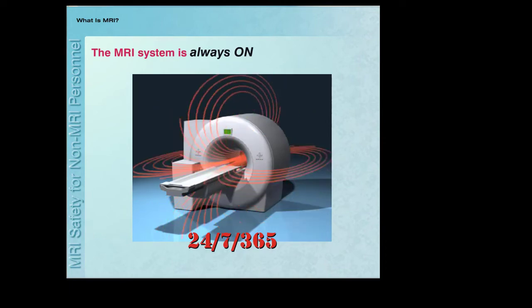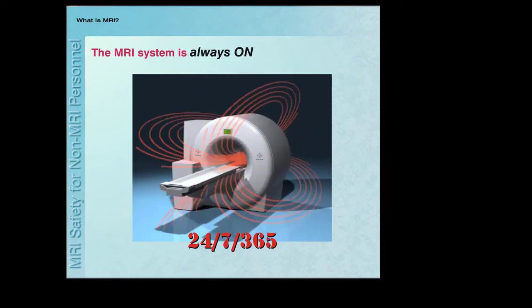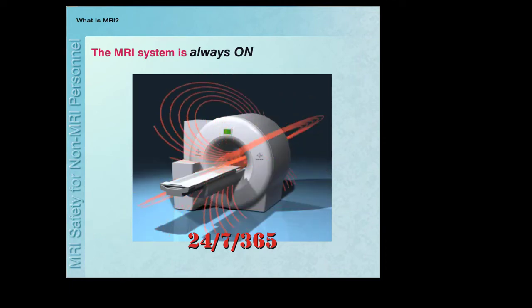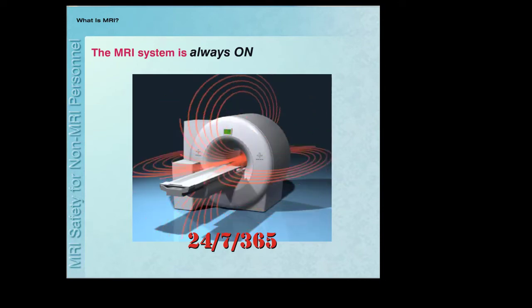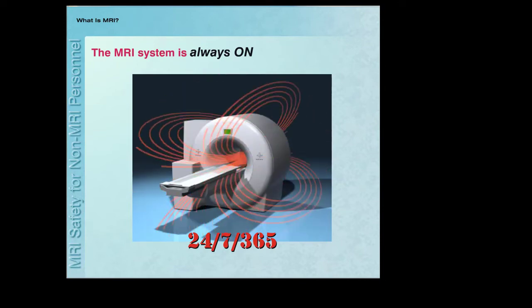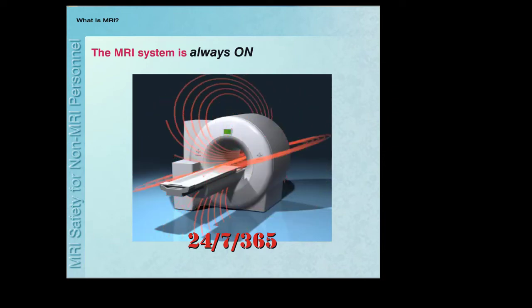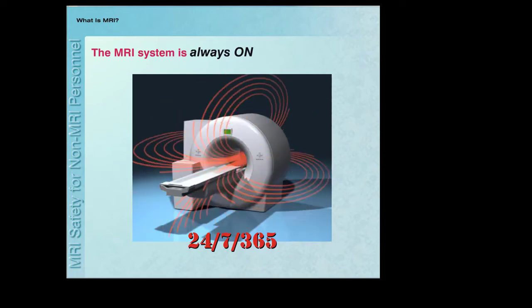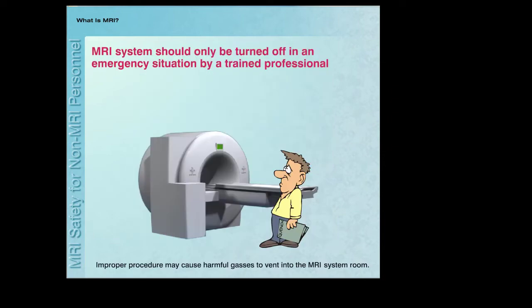If you enter the room where the scanner is located, you will be exposed to the magnetic field. Accidents often happen because people assume that the magnetic field of the scanner is off and mistakenly bring inappropriate metallic objects into the room. Most MRI system magnets can only be turned off, even in cases where emergencies exist, during a procedure known as a quench. A quench has negative and sometimes undesirable effects and should only be performed by trained professionals.